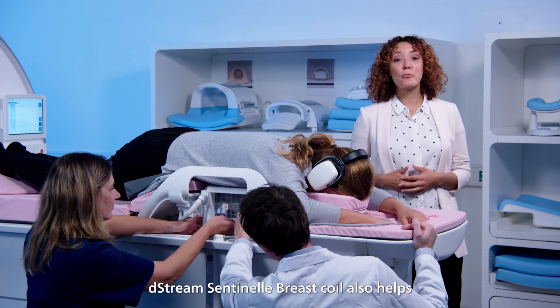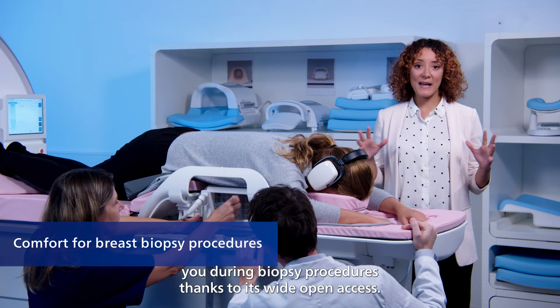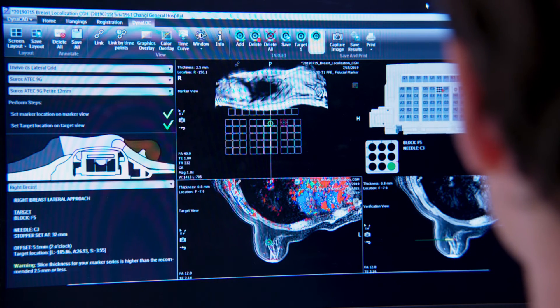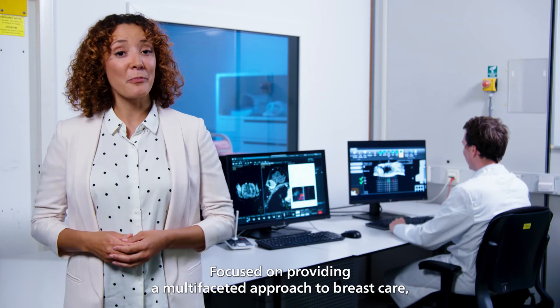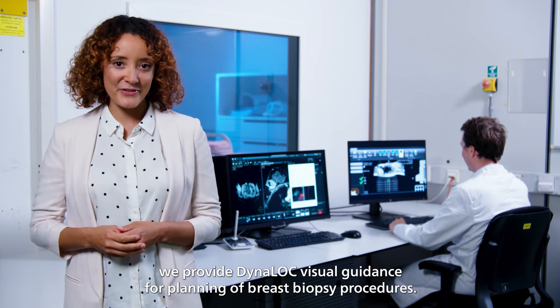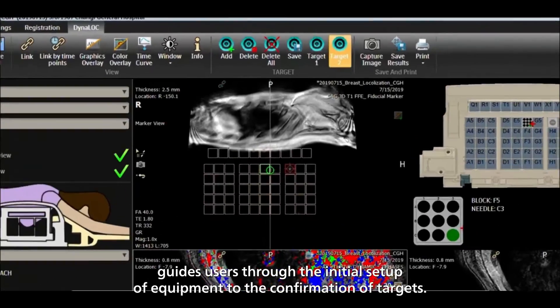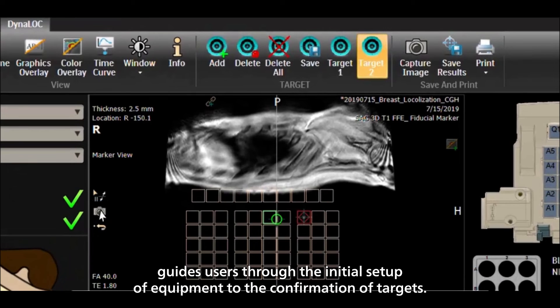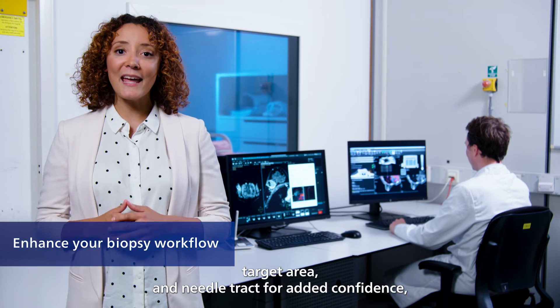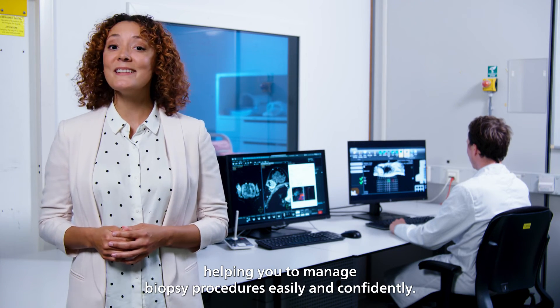The dStream Sentinelle Breast Coil also helps you during biopsy procedures thanks to its wide open access. It includes immobilization frames to support the biopsy grids. Focused on providing a multifaceted approach to breast care, we provide Dynaloc visual guidance for planning of breast biopsy procedures. Dynaloc's menu-driven interface guides users through the initial setup of equipment to the confirmation of targets. Computer renderings illustrate patient position, device setup, target area, and needle track for added confidence, helping you manage biopsy procedures easily and confidently.